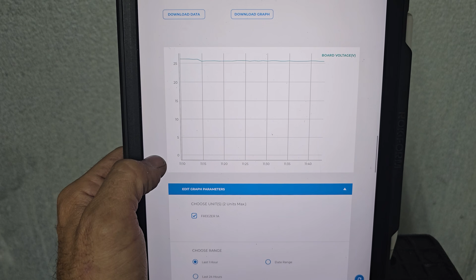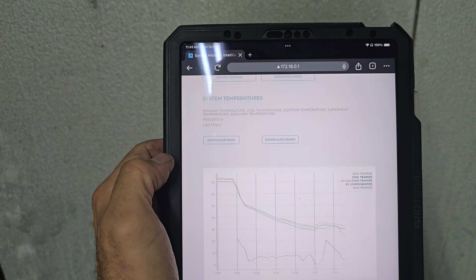Really cool. Another really important thing too, up on the side over here, is a transformer. You have to make sure you tap it right. This is a 208 volt system, so they come tapped for 240. So I tapped it so that way we can do what we need to do. But yeah, perfect. All right, well, we're just waiting for it to come down to temp.